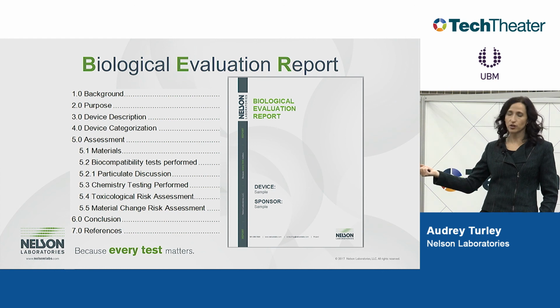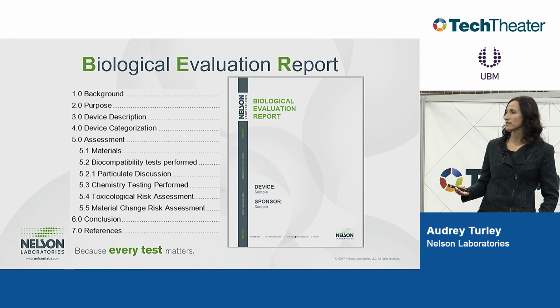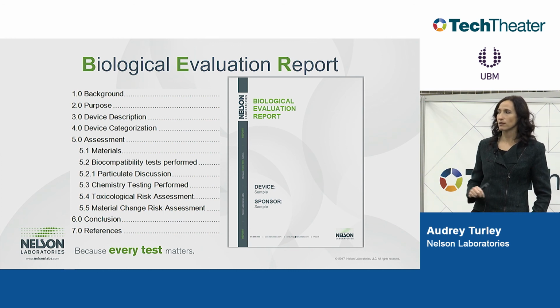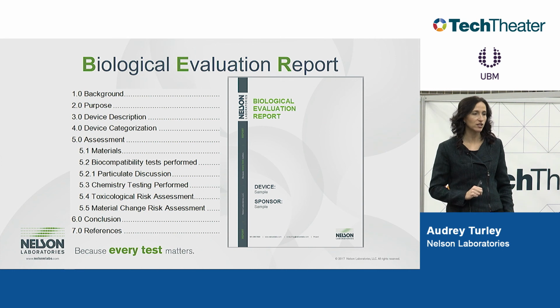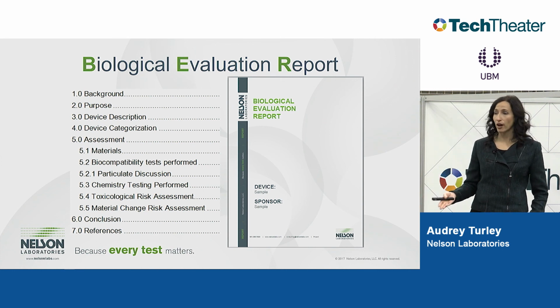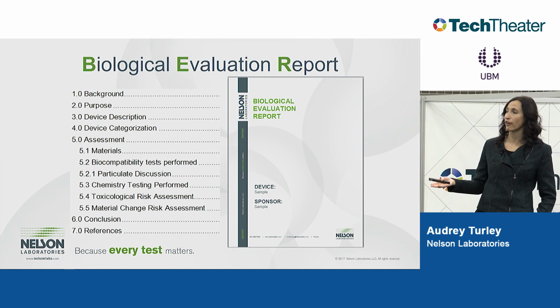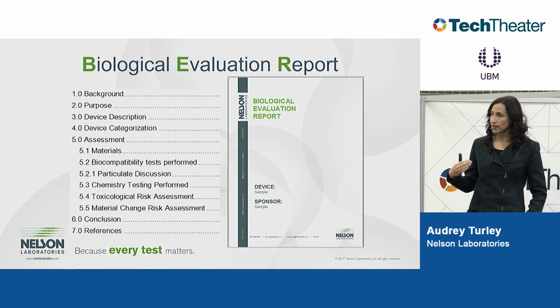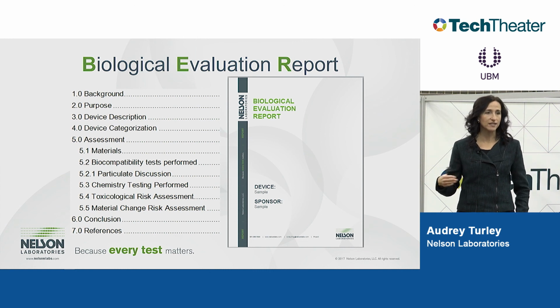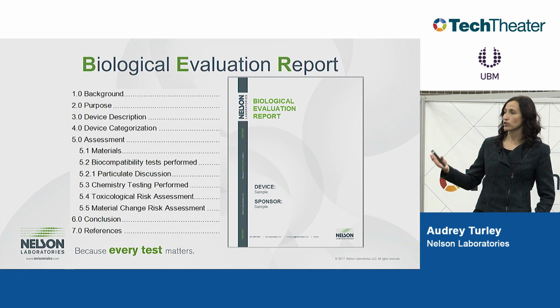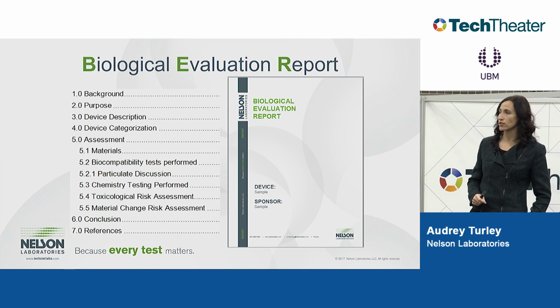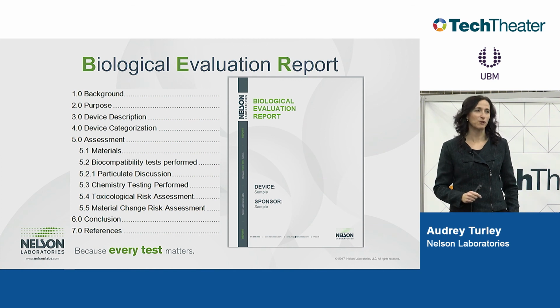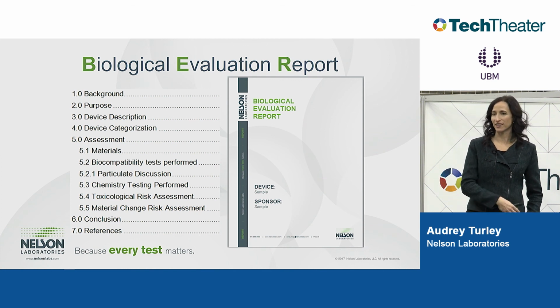So again, we would do a material characterization, talk about your materials. You cannot state this enough in your presentations to them. Talk about your biocompatibility tests. I put this particulate discussion in here because sometimes we see particulates in biocompatibility extractions. Have a conversation about that. Maybe do some additional particulate testing on those extracts and eliminate or mitigate the risk right here instead of waiting to see if they catch it. Just have the conversation up front. Talk about your chemistry testing, your toxicological risk assessment, and then, of course, a material change assessment, because it may have changed between the testing completion and submission. You can have this all wrapped up in one package for the agency.